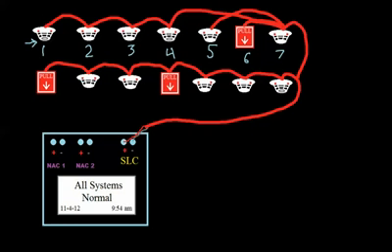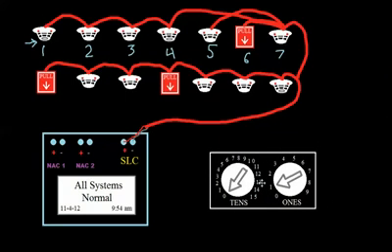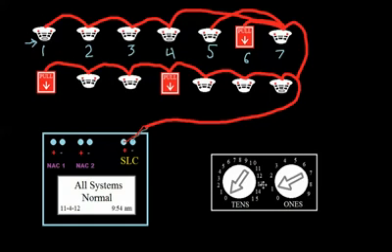Well, I'd have to set an address on each one of those, and I'm going to show you how that works with most panels. Like I said, I'm basically going to be drawing a lot of stuff that relates to Fire-Lite and Notifier because that's what I'm used to. On all the panels, you have to somehow give these an address, but it varies how you do that from manufacturer to manufacturer. But for Fire-Lite and Notifier, this is typically how it's done. You see these two dials, and this would be on the back of the devices, or in some cases on the pull stations it'd be on the front of them. But there's a tens place and a ones place. The tens place goes all the way up to 15. The ones place goes to 9.